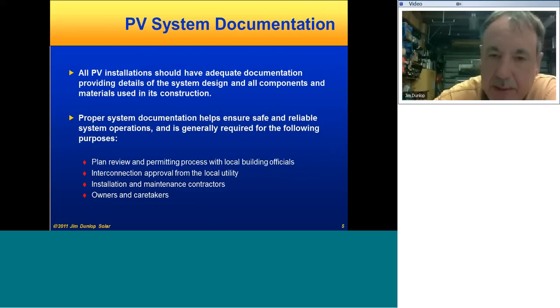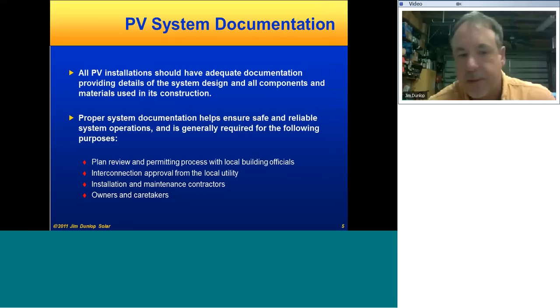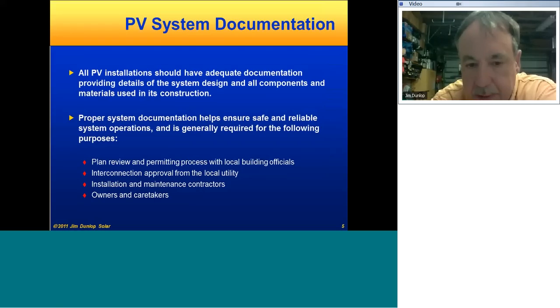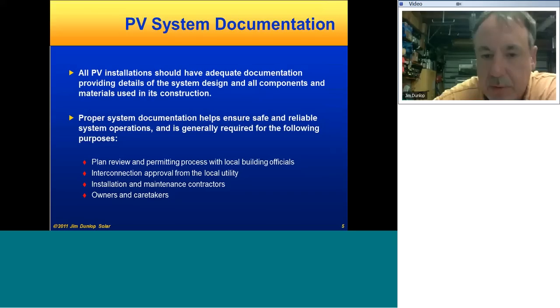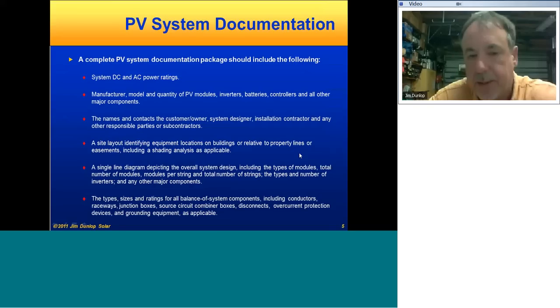The first thing the standard addresses is the documentation aspects, which are really the whole key to safely and successfully commissioning, operating, and maintaining a system. Obviously the details of all the design and components and documentation are important for so many reasons: for the regulatory approvals with the building officials and utility interconnection, as a guide for the contractors when they're installing the equipment, and as a reference for the owners and caretakers of the system over its life.